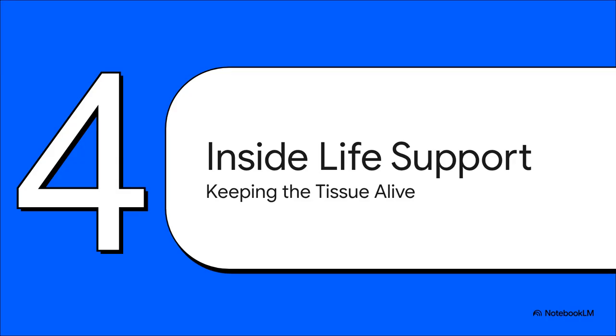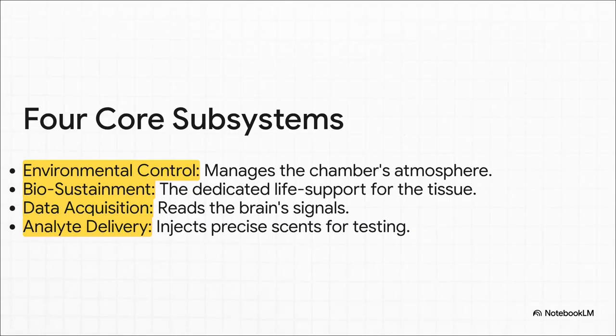Well, let's peek under the hood. It's essentially a super sophisticated life support system, and its whole job is to keep that piece of brain tissue alive and functioning perfectly during the tests. And it all boils down to four core subsystems. First up, you've got environmental control, which manages the entire atmosphere inside the chamber. Then there's biosustainment, which is the dedicated life support, keeping the tissue healthy. Third is data acquisition. That's the electronic side of things, how the machine actually reads the brain's signals. And finally, you have analyte delivery, which is the incredibly precise system for injecting the scents for testing.